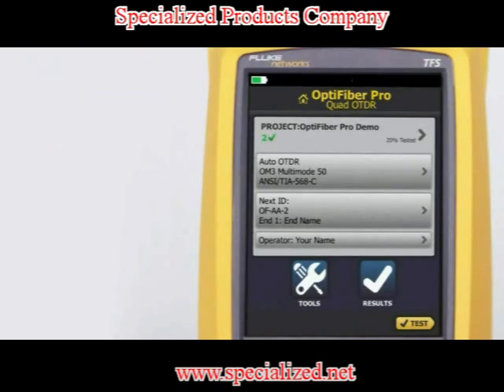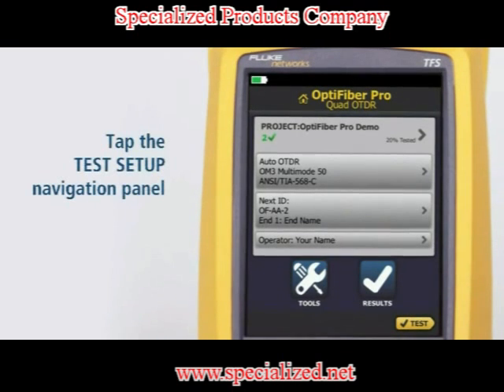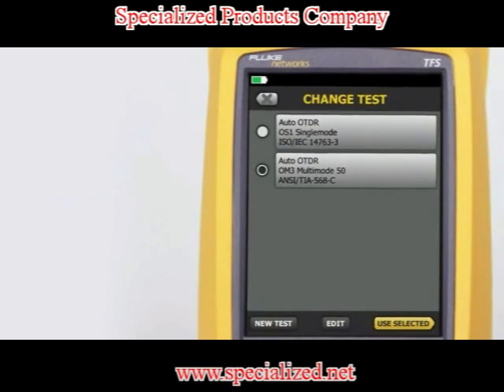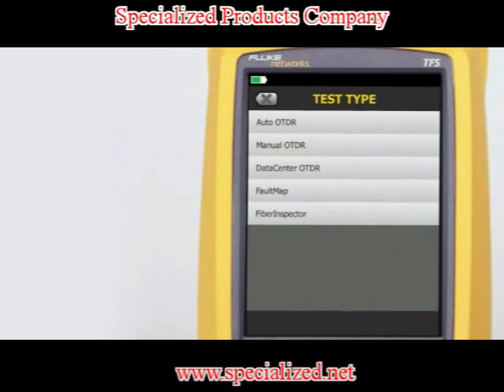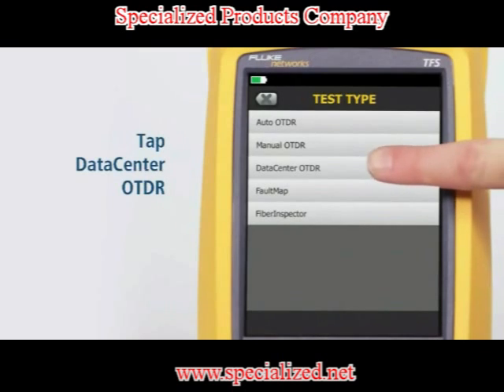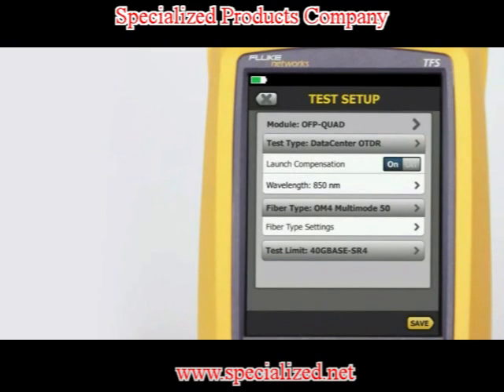The Data Center OTDR test mode is optimized for fiber installations that have short links, many connections, and the possibility of large reflections. Tap the test setup navigation panel, then tap New Test, then tap Data Center OTDR. Note that the Data Center OTDR defaults to only 850 nanometers for multi-mode fiber and 1310 nanometers for single-mode fiber. These are the wavelengths typically used in data centers. Tap Save.